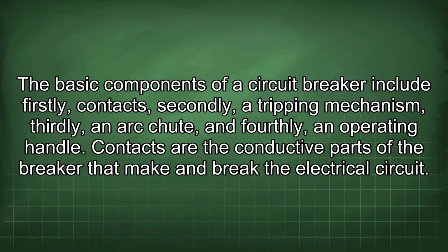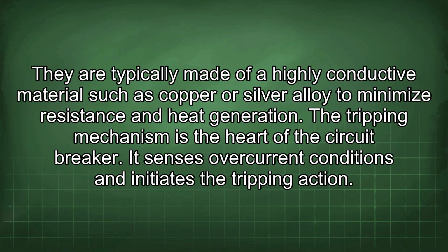The basic components of a circuit breaker include: firstly, contacts; secondly, a tripping mechanism; thirdly, an arc chute; and fourthly, an operating handle. Contacts are the conductive parts of the breaker that make and break the electrical circuit. They are typically made of a highly conductive material such as copper or silver alloy to minimize resistance and heat generation. The tripping mechanism is the heart of the circuit breaker.